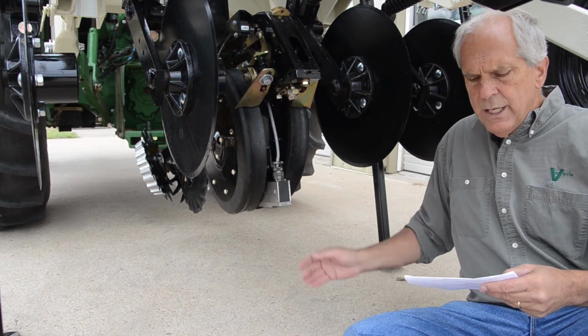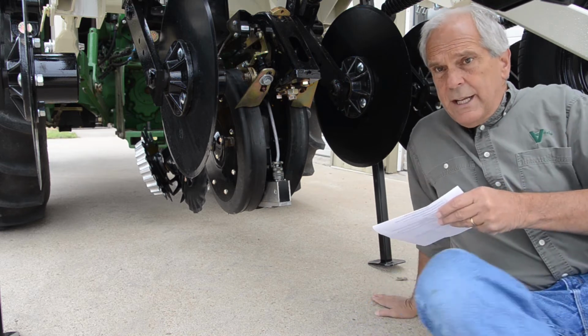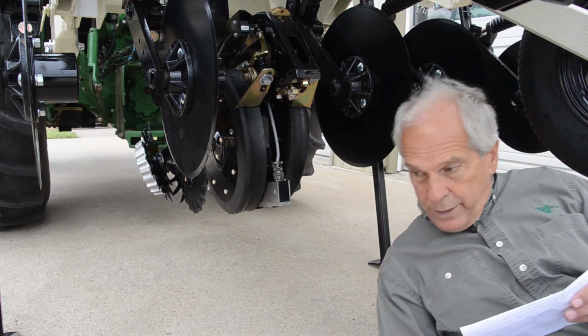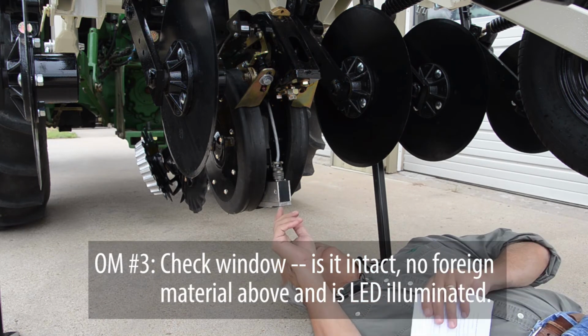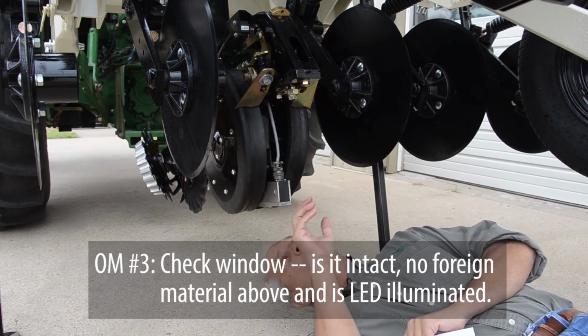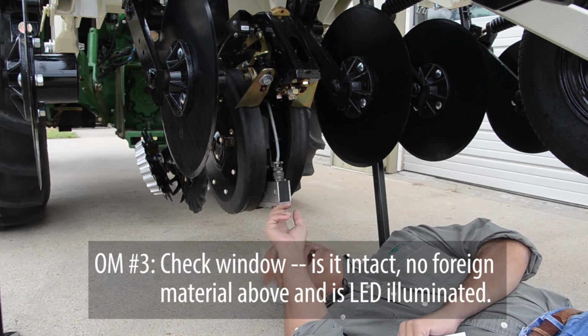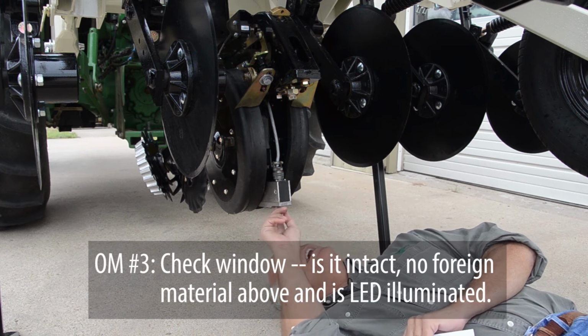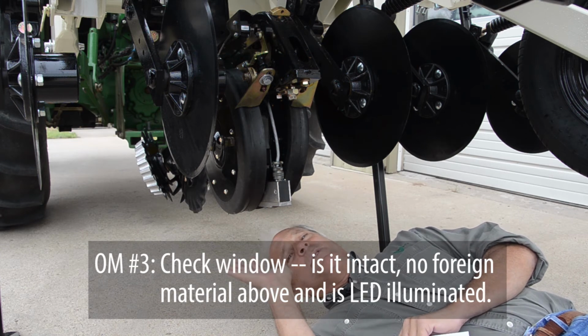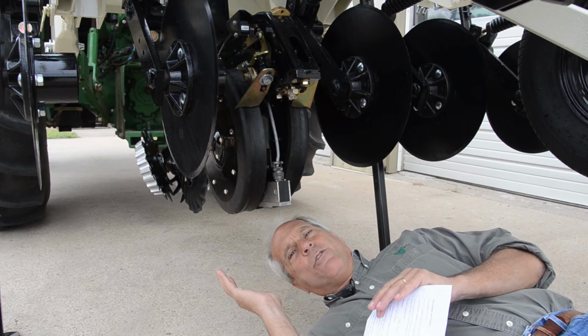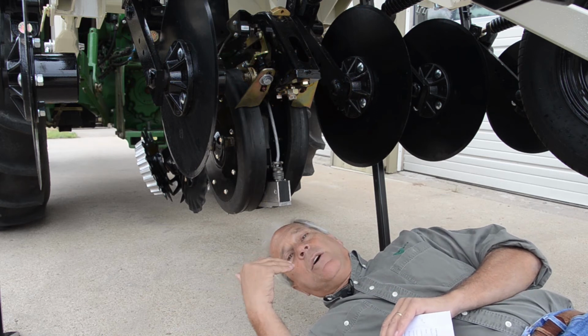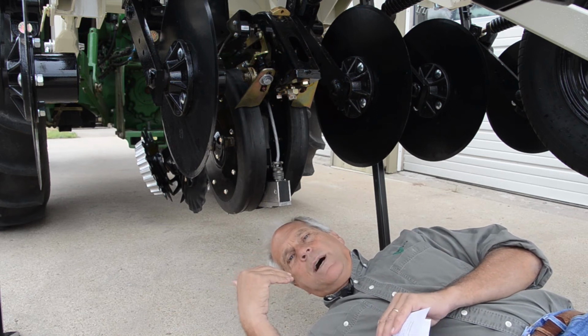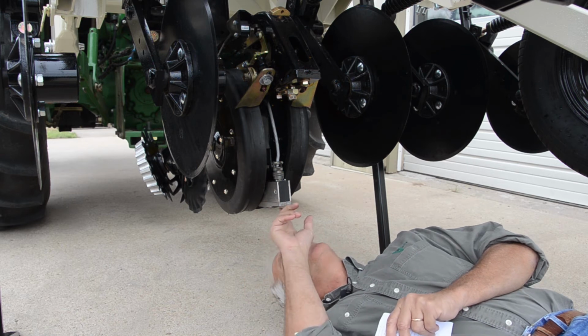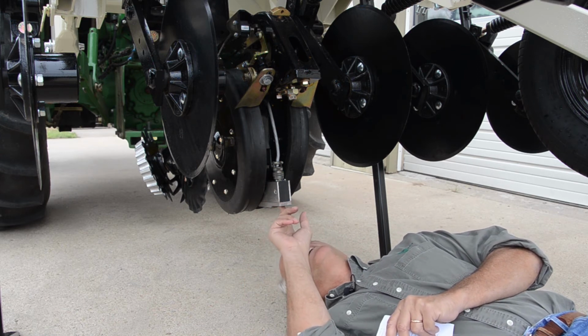For this one, it's really important to get under and actually look right up at the window. It's really the only way to tell if there's any crack in the window or any foreign matter that's somehow gotten in there above the window, between the sensor and the window. If there's any foreign matter above the window, that will also wreak havoc with your data. So that's really the only way to do it, is to get under that.